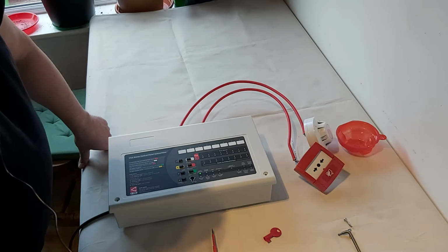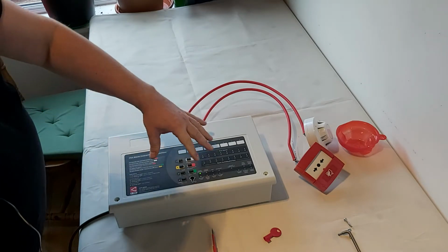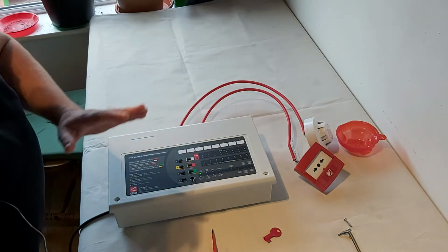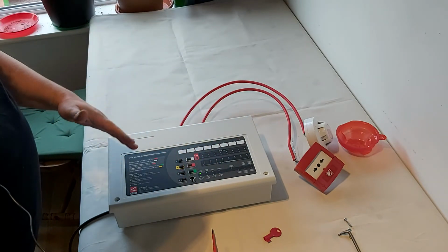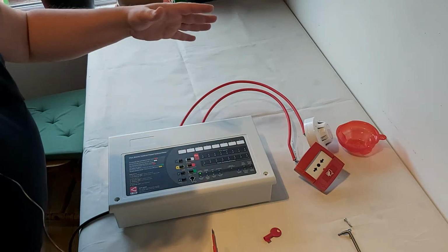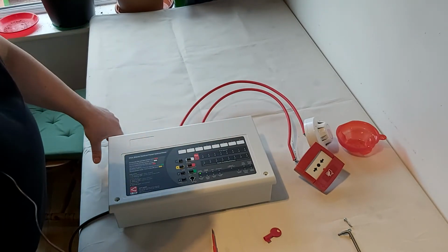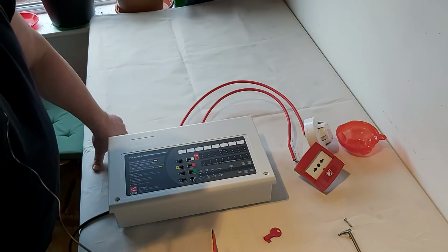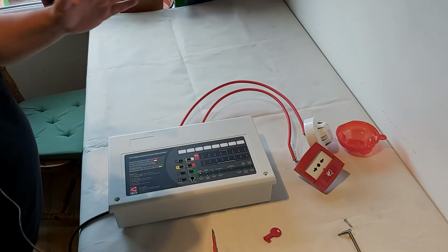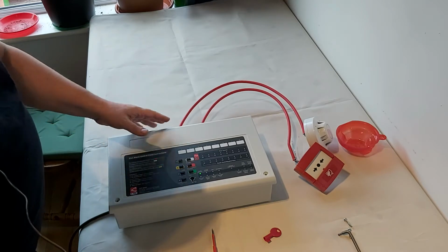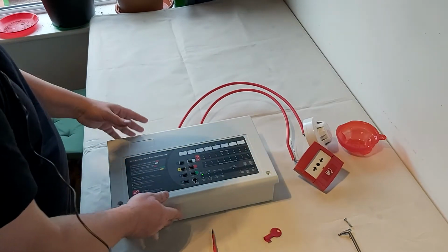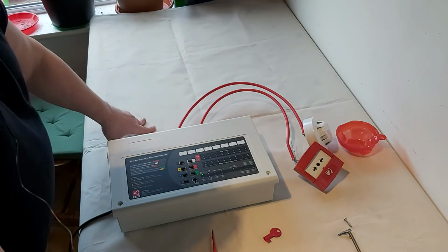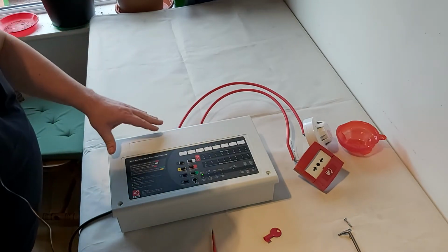And the third function is to send a signal to monitoring station, which is to trigger an output on this device, and then in a small installation, usually this output is connected to the intruder, and intruder sends signal to monitoring station, or you can call it alarm receiving center, through their communication device. Typically, fire alarms don't have a communication device. Doesn't mean they cannot, just that's general practice in Ireland and probably UK.